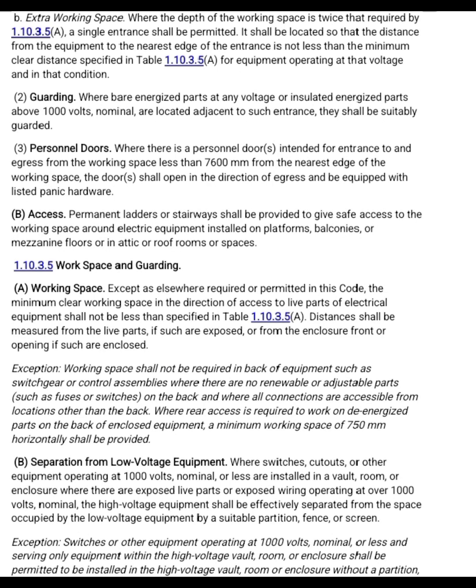B. Extra working space, where the depth of the working space is twice that required by 1.10.3.5a. A single entrance shall be permitted. It shall be located so that the distance from the equipment to the nearest edge of the entrance is not less than the minimum clear distance specified in the table 1.10.3.5a for equipment operating at that voltage and in that condition. 2. Guarding, where bare energized parts at any voltage or insulated energized parts above 1000 volts nominal are located adjacent to such entrance, they shall be suitably guarded.